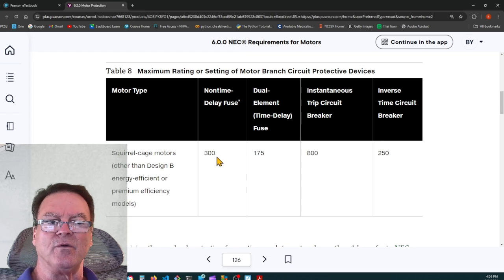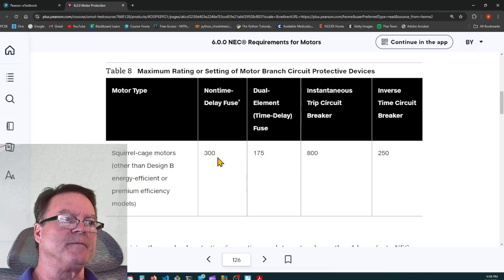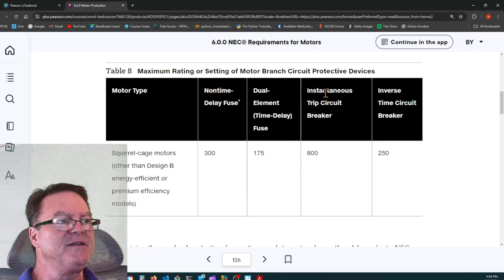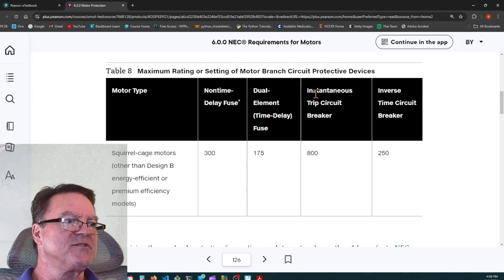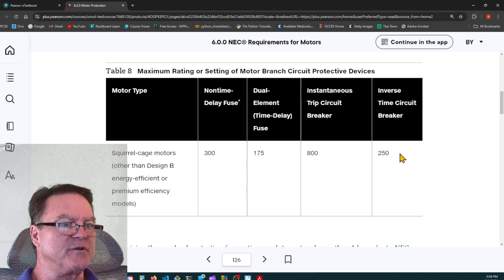Tables 430.247, 248, 249, and 250. Dual element time delay fuses, 175%. Instantaneous trip circuit breaker, 800%. That's why we don't like to use instantaneous trip circuit breakers to protect motor circuits. Inverse time circuit breakers, 250%.